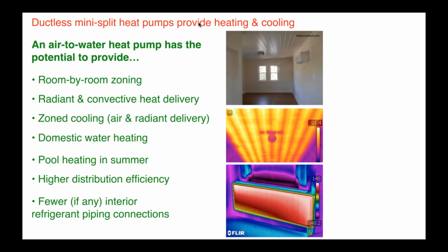You have the advantage of much higher distribution efficiency on moving that energy around through the building. And you don't have, at least in the case of a monoblock, you really have no refrigerant inside the building. With a split system, you do have a small amount of refrigerant inside the system as a whole, but compared to a large VRF system, much, much less refrigerant in the system. So a lot of advantages there, okay?